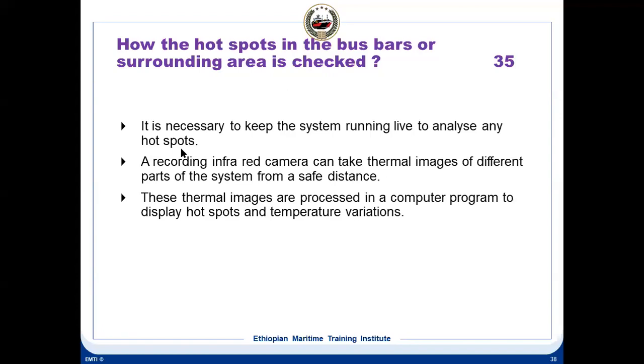In high voltage equipment switchboards, you will find at the backside a window is provided. Through this window, you can use an infrared camera. Normally, they supply these infrared cameras on high voltage ships. Through these windows, you can take a thermal image of each hot spot on the bus bar. So this camera can identify: is there any hot spot? If there is a hot spot, that means something is loose on the bus bar. You have to isolate that particular section of the switchboard and correct it, or tighten it up.